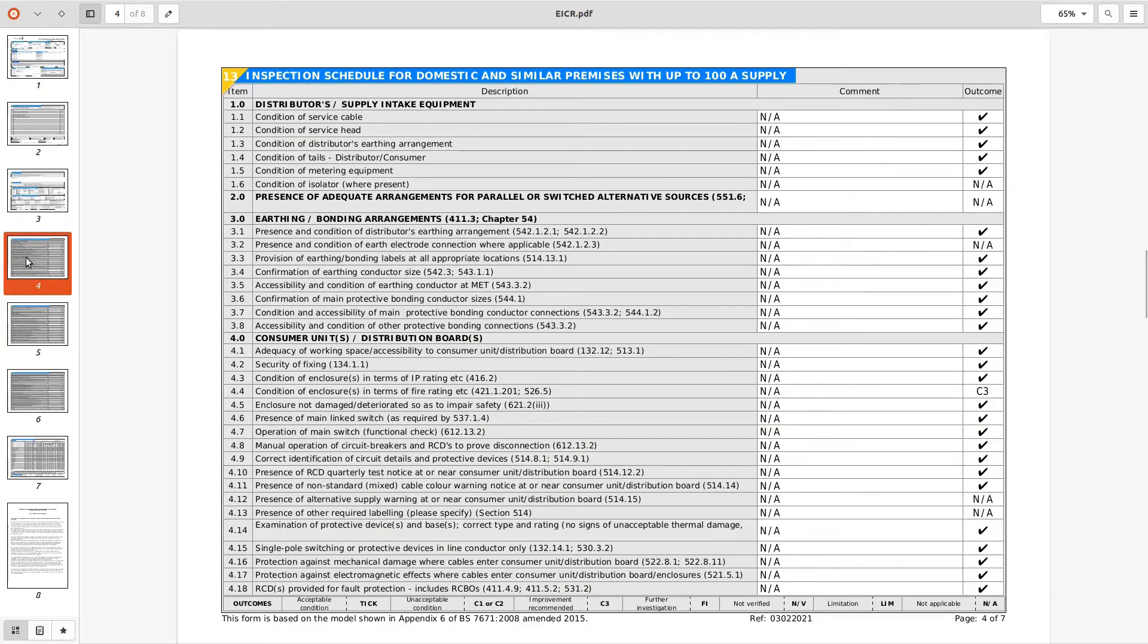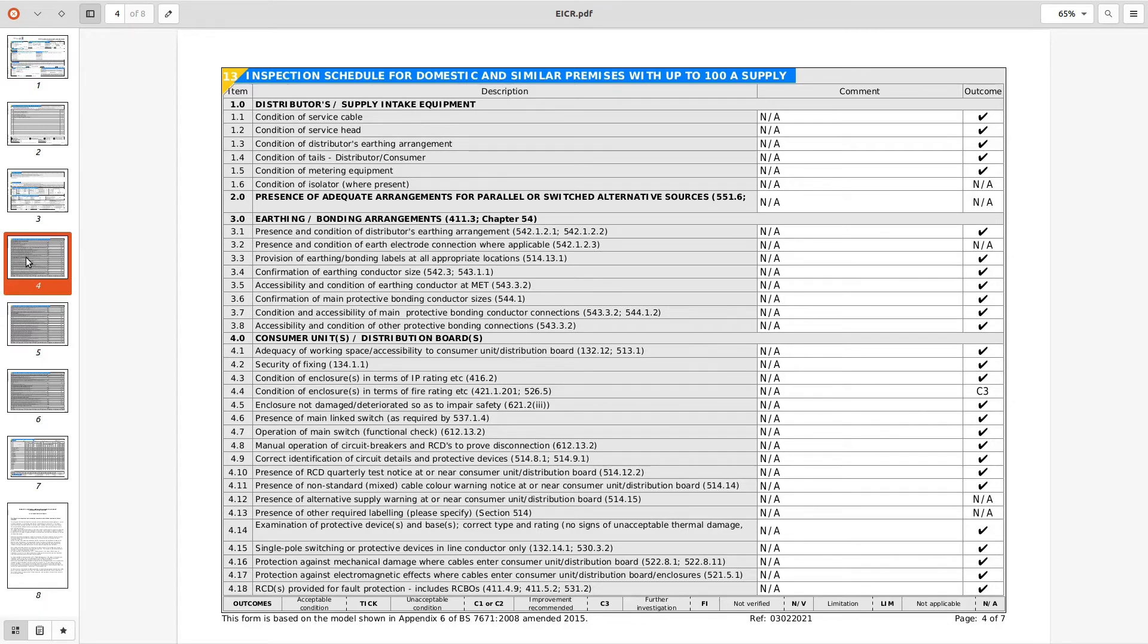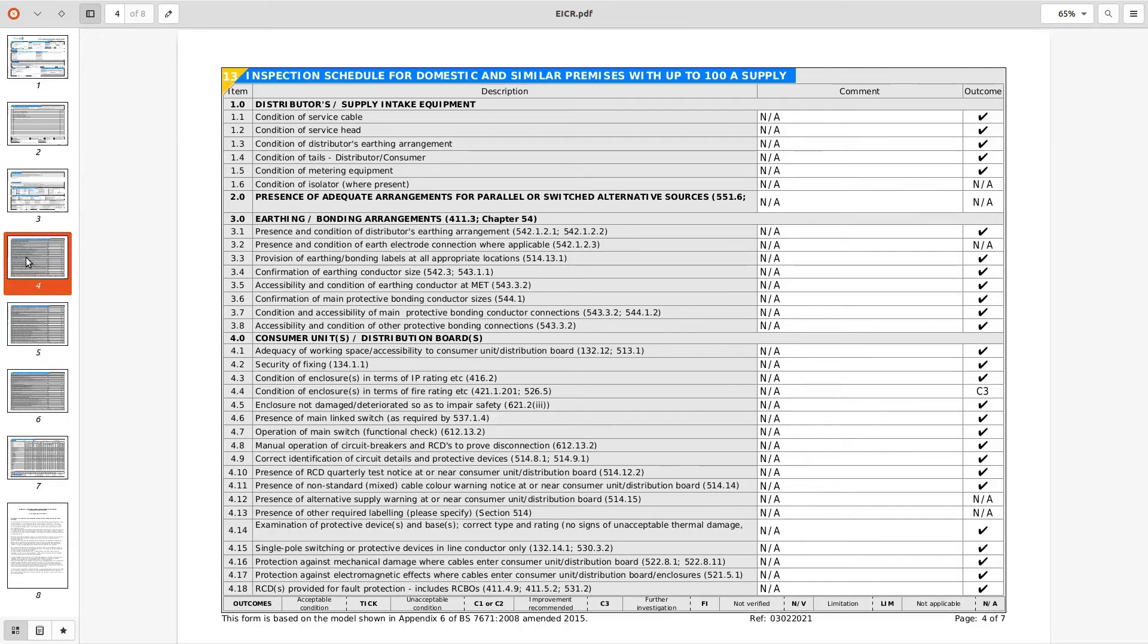Looking at the schedule of inspections, I'm not going to go through all these but we'll just take a look at some things that we think may be right or may be wrong. Let's have a look first thing down on the list, so we've got 5-1, sorry not 5-1 I've gone ahead of page, say that again I've gone ahead of myself all of a sudden. 3.8, accessibility and condition of other protective bonding conductors he's put a tick in there. I don't think there is any other bonding conductors, he said certainly detects gas and water, so just not applicable would have been all right in there I suppose.